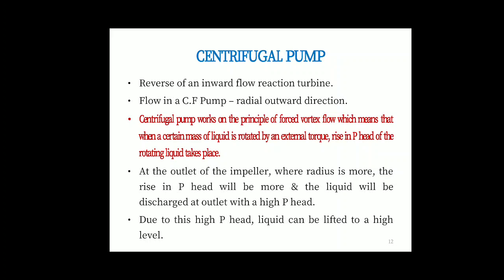Now let us see a centrifugal pump. It is the reverse of an inward flow reaction turbine. Flow in a centrifugal pump is radial outward direction. Centrifugal pump works on the principle of forced vortex flow, which means that when a certain mass of liquid is rotated by an external torque, rise in pressure head of the rotating liquid takes place. At the outlet of the impeller, when the radius is more, the rising pressure head will be more and the liquid will be discharged at outlet with very high pressure heads. Due to this high pressure head, liquid can be lifted to a high level.